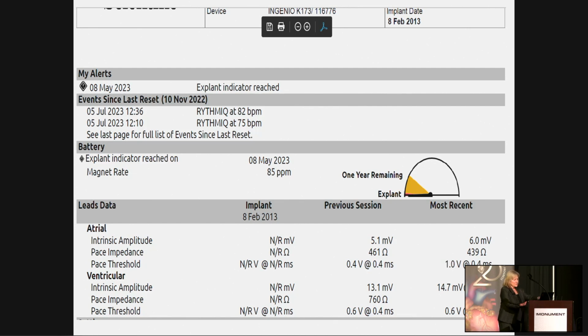You can see the magnet rate on her pacemaker was down to 85. On brand new ones, the magnet rate will be 100, and that means when you put a donut magnet on, it'll switch to fixed pacing and pace at 100 beats a minute. As the battery ages, that magnet rate will come down. And then you also see on the bottom the intrinsic amplitude of the P wave and the R wave, and also the pacing thresholds, what they've gotten when they've tested.